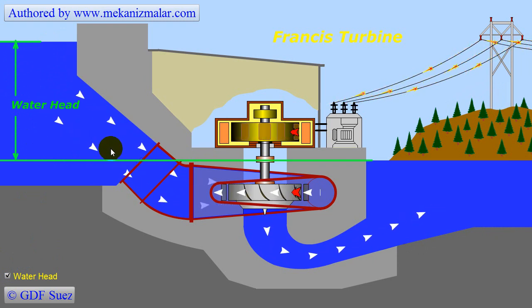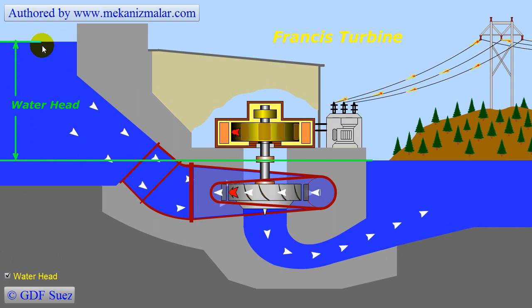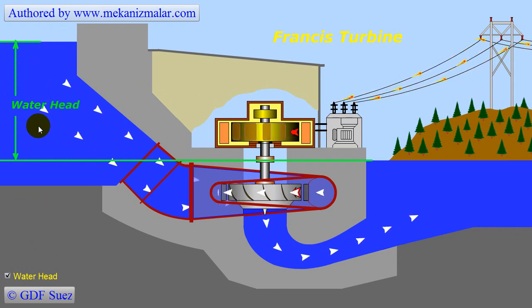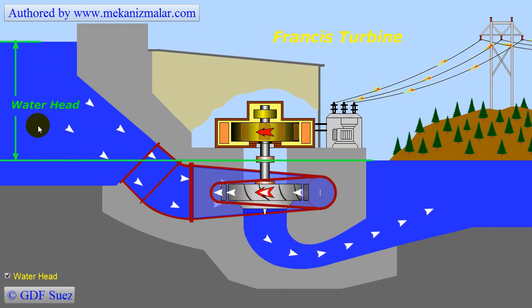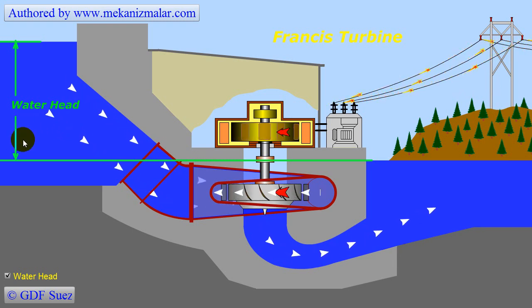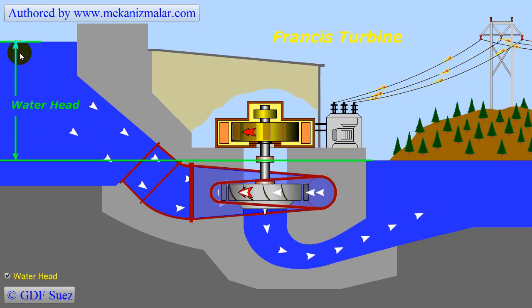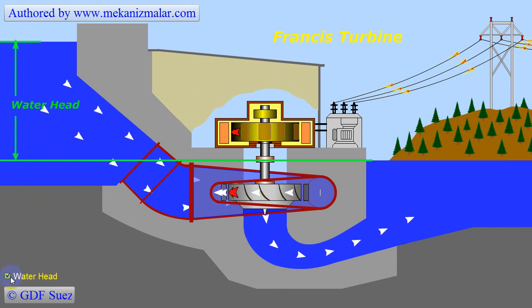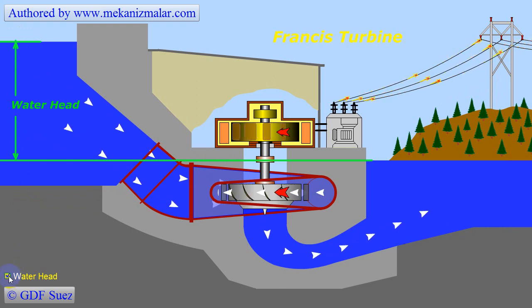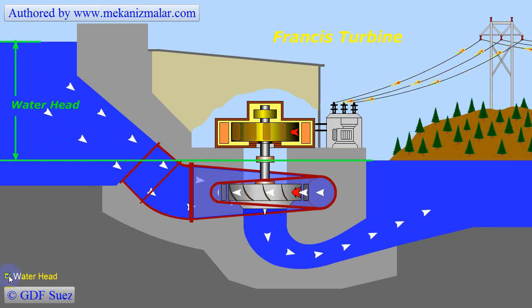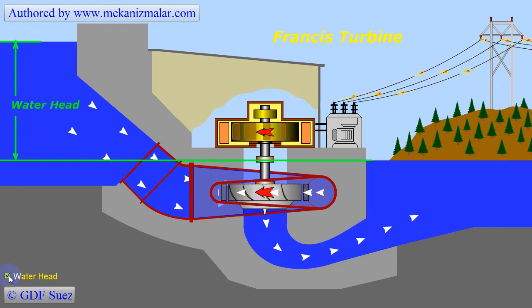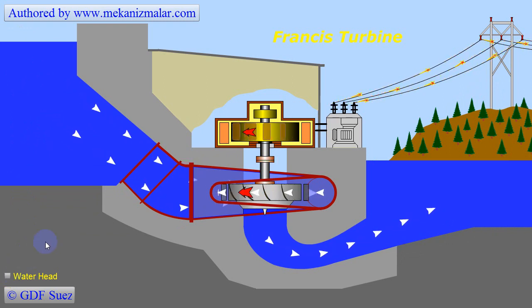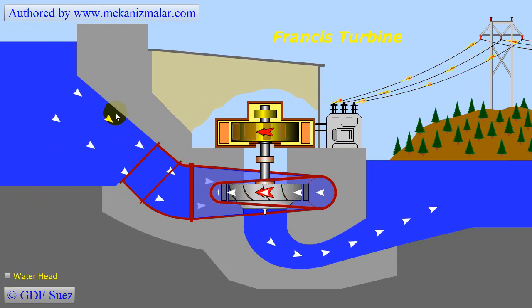The Francis turbine fills a large gap between the Pelton and Kaplan and it is widely used. They operate in water heads from 10 to 600 meters and are primarily used for electric power generation. Their power output can be calculated from the water head and flow rate, and typically ranges from 10 to more than 700 megawatts.